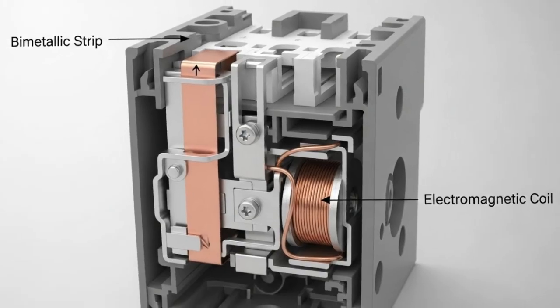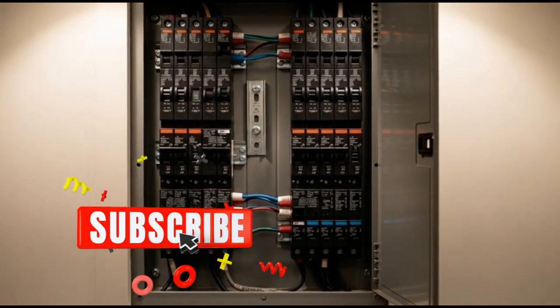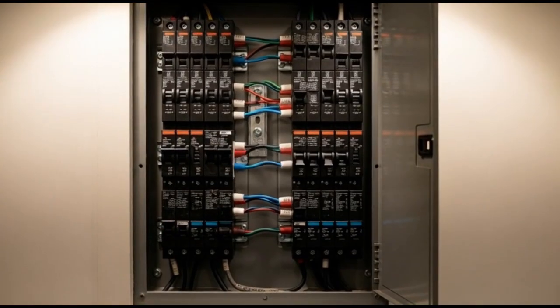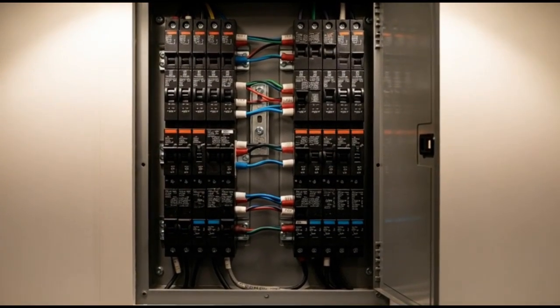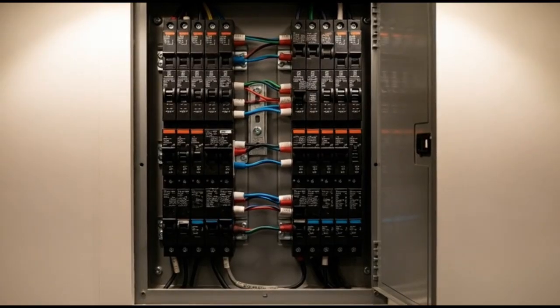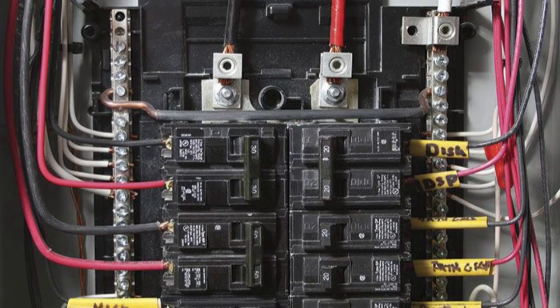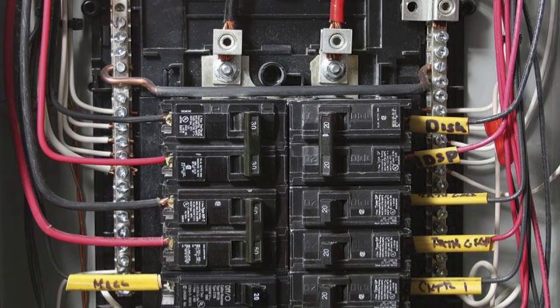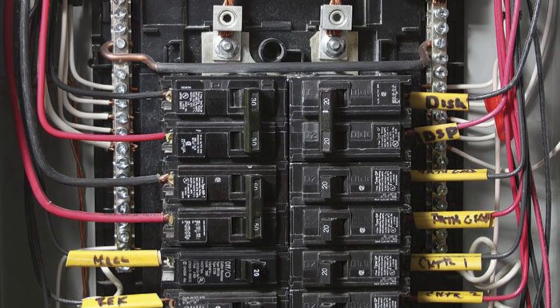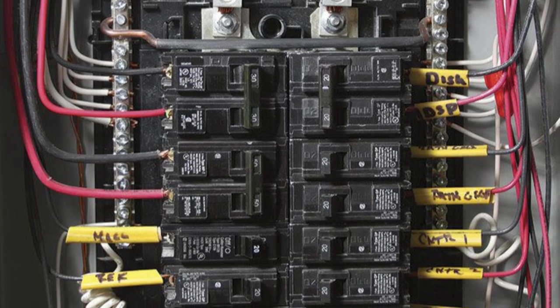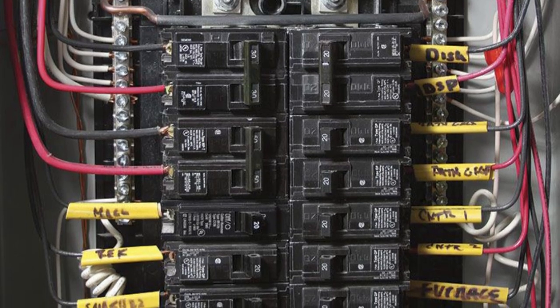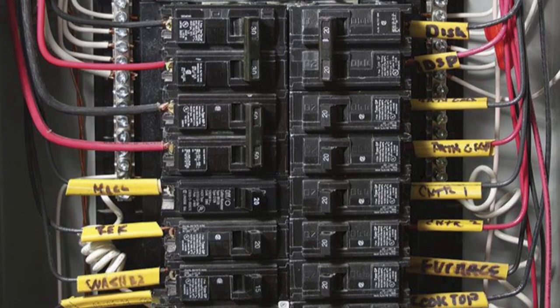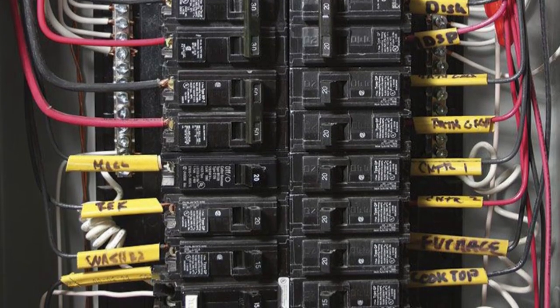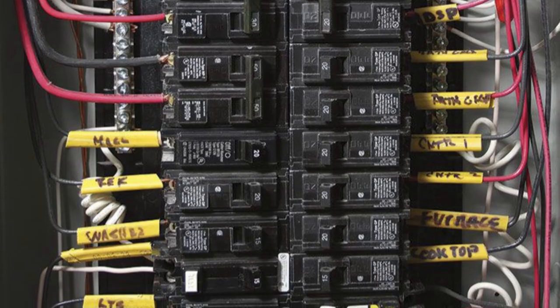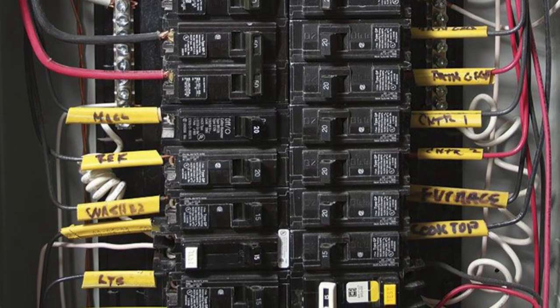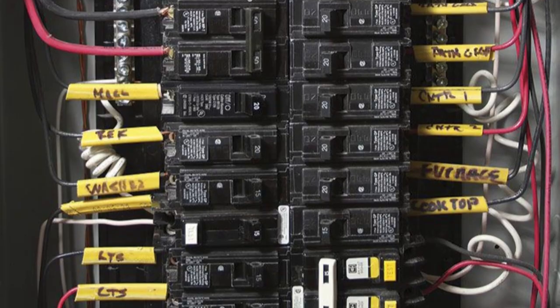When a main breaker starts failing, it often trips at lower and lower current levels. The breaker no longer accurately measures the load. It might trip at 80 amps when it's rated for 200, or it might trip randomly even when current flow is well within safe limits. A failing breaker can also trip from internal arcing. As the contacts inside the breaker wear down, they don't make clean connections anymore. Small arcs jump across the damaged contacts. The breaker detects this as a fault and trips. If your main breaker is more than 20 to 25 years old and trips without explanation, the breaker itself may be the problem.